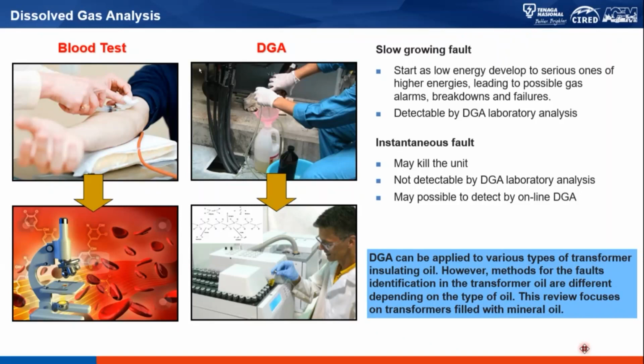We can know in real time, much sooner compared to manual oil sampling. I'm talking in advance here about online DGA monitors, which we'll discuss later in this presentation. I just wanted you to be aware that not every fault can be detected by DGA, even though 50% of incipient faults can. But there are always faults out there that are instantaneous, so perhaps we need a change in practice to now install online sensors for better monitoring of the transformer's condition.